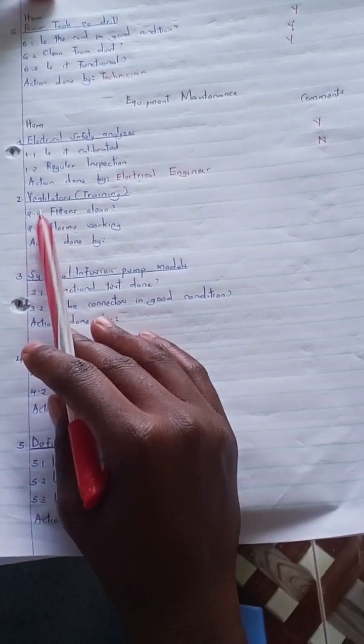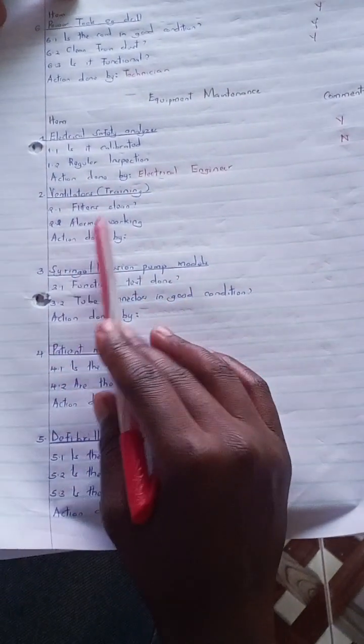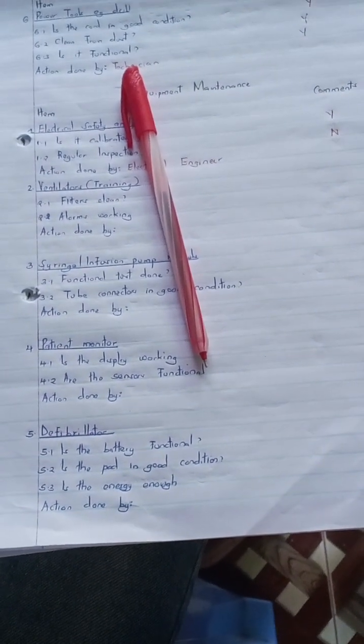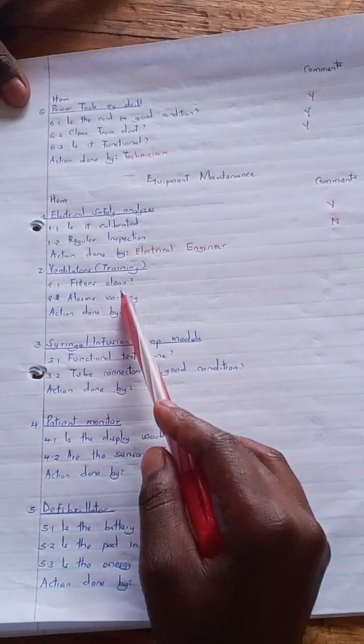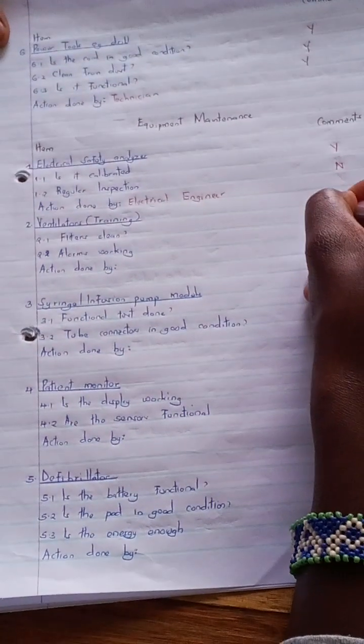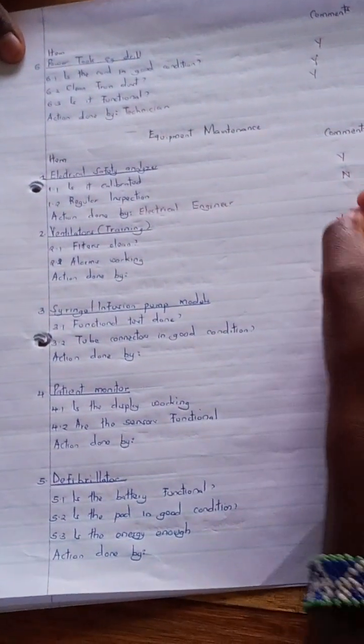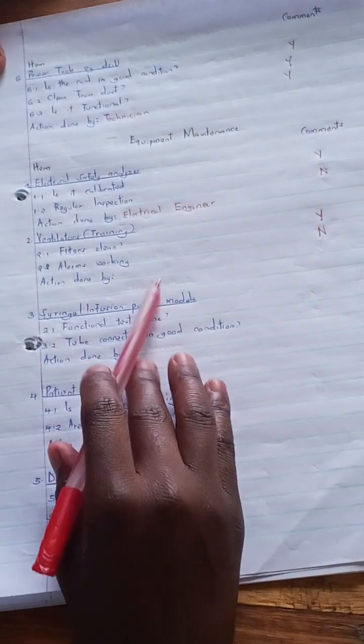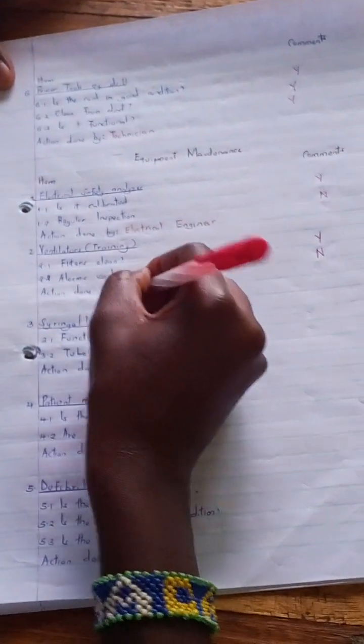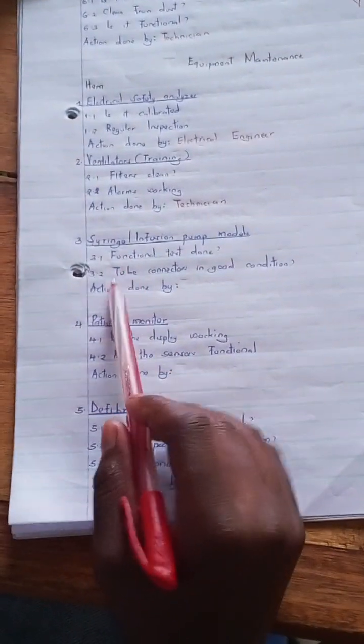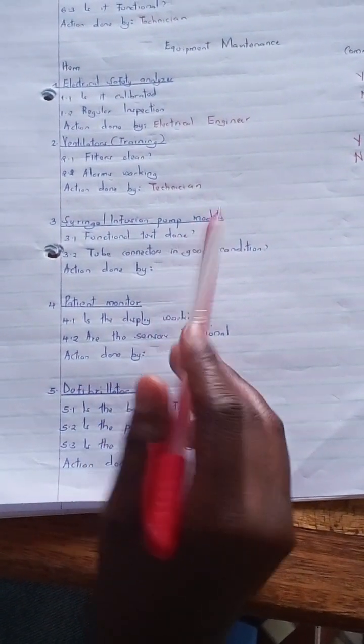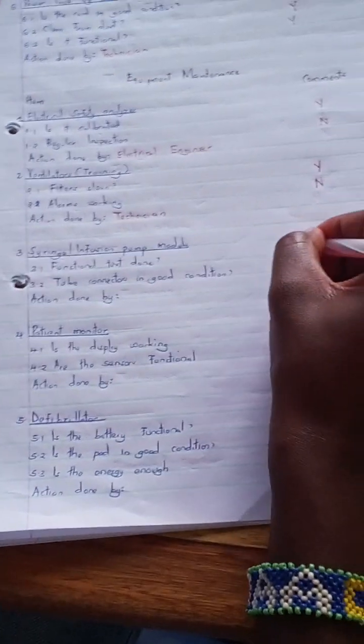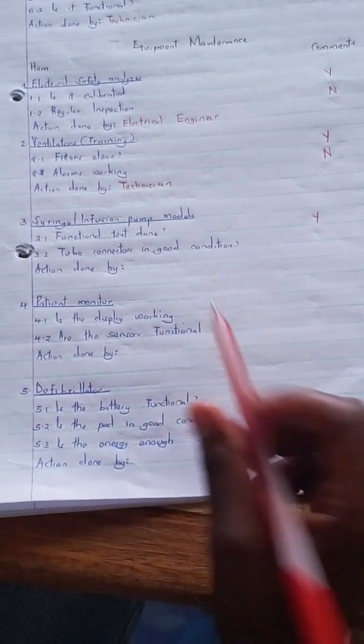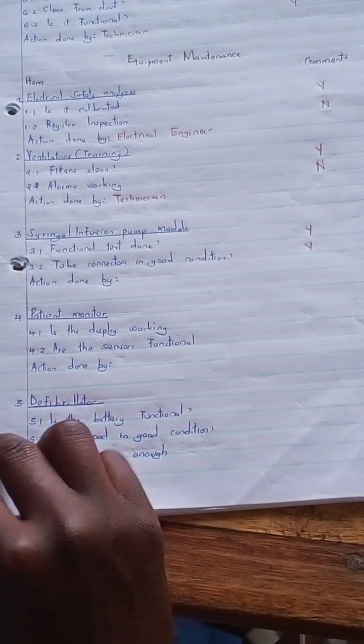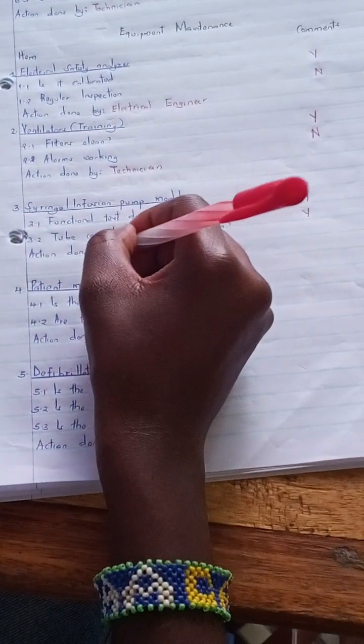Now we go to the equipment number 2, like the ventilators for training. Are the filters clean? Yes. The filters, are they clean? When we say yes, when they are clean. The alarms, are they working? When they are not working, we will say no. We will indicate N. The action done by maybe a technician. Then we go to the equipment number 3, that is the syringe or infusion pump models. Are they functional? When they are functional, we will say yes. Tube connectors in good condition. When they are in good condition, we will place our Y. That's yes. The action done by maybe a student attaché.